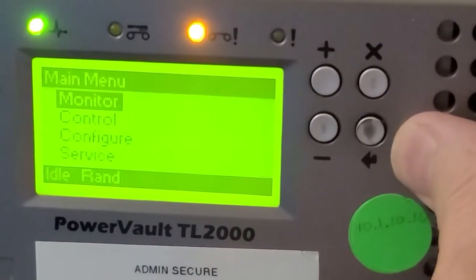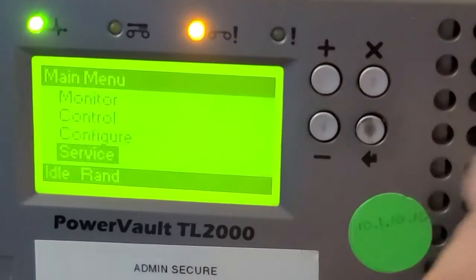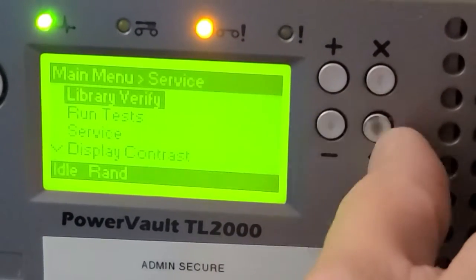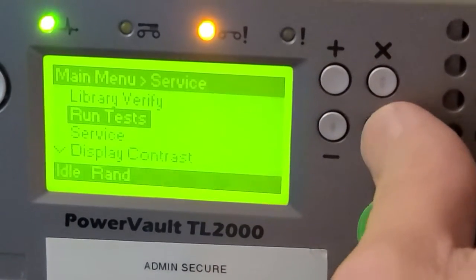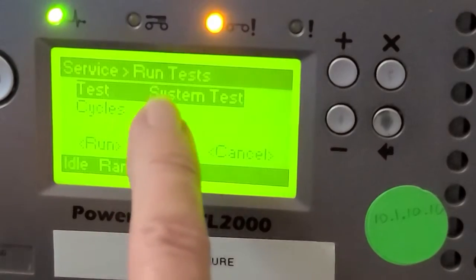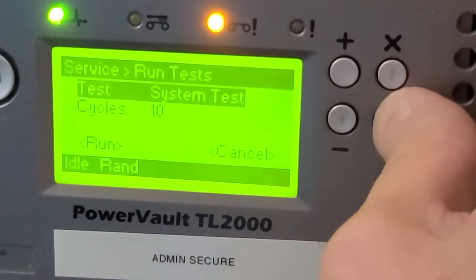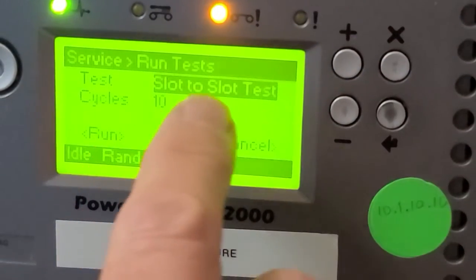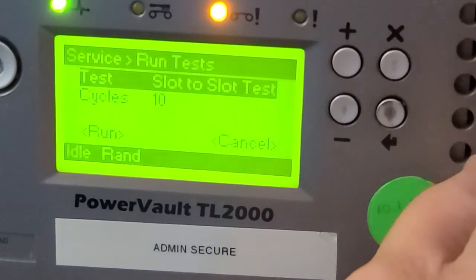Hit Enter. Arrow down to Service. Hit another Enter. Go down one to Run Tests. Hit another Enter. We now have the System Test selected. Hit an Enter there. Arrow down to the slot-to-slot test. Another Enter to accept that.